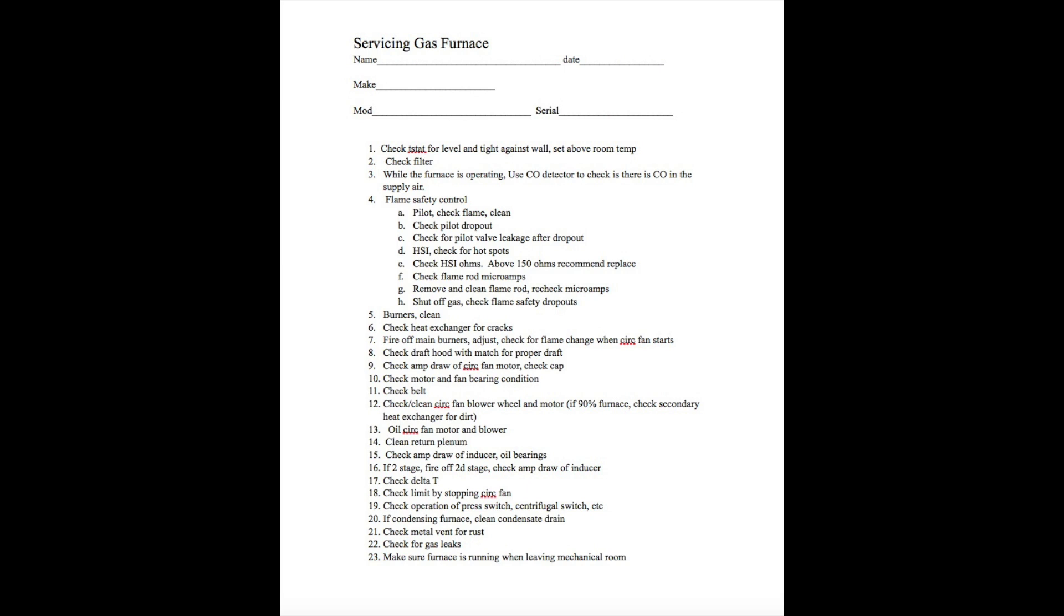We're going to fire off the main burners. We're going to adjust, if there is a primary air adjustment on the burners, you need to adjust it to get rid of the yellow tips. Now, we're going to check for flame change when the circulating fan starts. This is important. If the flame changes when the fan starts, it means there's probably a crack in the heat exchanger. We're going to have to look real close. The fan doesn't start right away. It takes 30 to 45 seconds to start. So when that fan starts, you'll be watching those burners to see if there's any change in the burners.